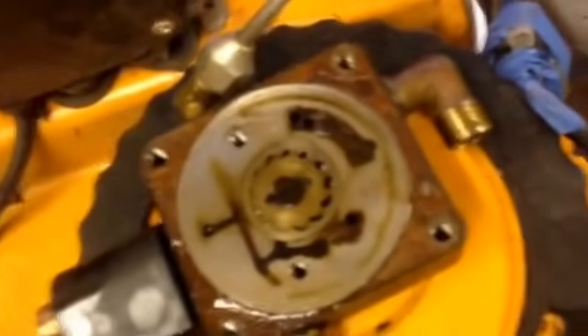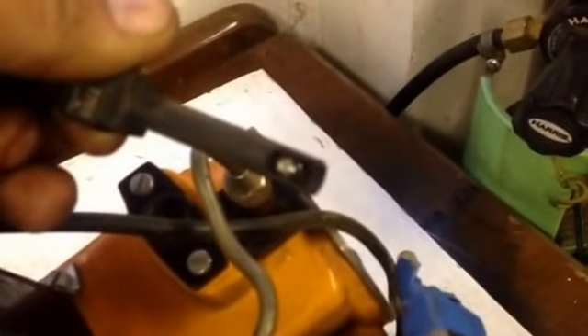Right, if this runs and it doesn't see the flame - so it runs, it sparks, it lights, and then it goes out - quite often what's happened is that this little magic eye here, you see it's got a little light sensing diode there, gets covered in crap. Warning though, if that's getting covered in muck, that is probably because this thing is burning badly, because this should not be in an area where it gets covered in muck. So if this is getting covered in muck, you can fix it by just clearing it, just wiping it clean. But you've got a further problem, because no soot should be getting this far back - this should be in clean air. But yeah, just wipe that clean. More often than not, these don't get filthy, they blow, and something - they just don't work anymore.